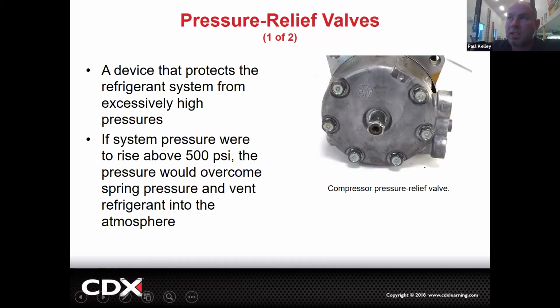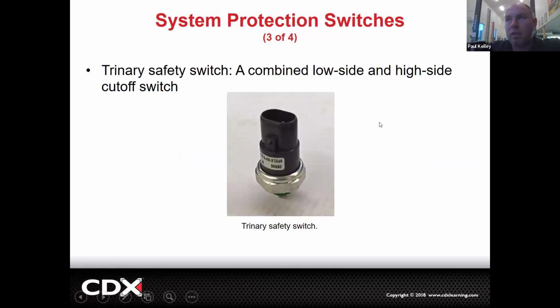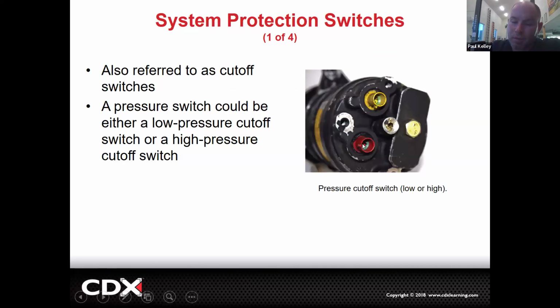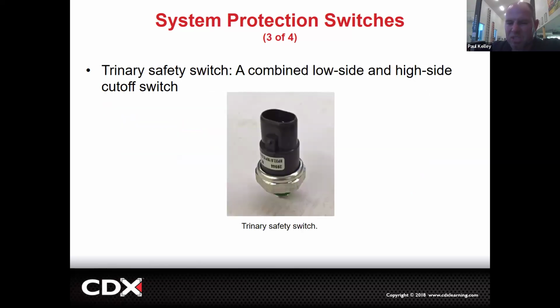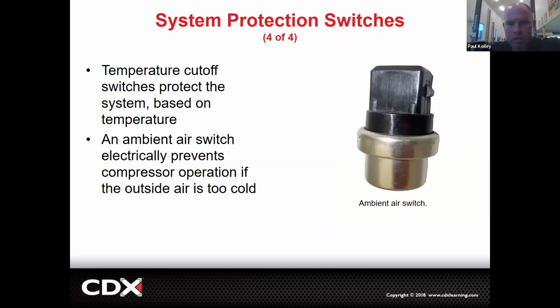So you may or may not see a compressor relief valve, and you may or may not see a high pressure cutoff switch. It may have one or the other, but probably not both. And sometimes neither, because this is a trinary switch. It's a combined high-low side cutoff switch. A lot of times they'll put it in a location, or they can be kind of funny. Sometimes they even do temperature cutoff switches.